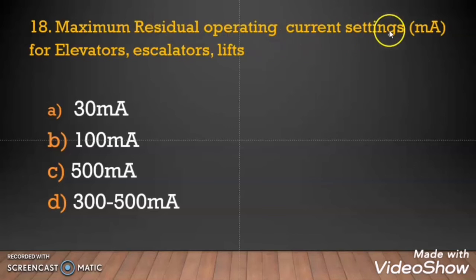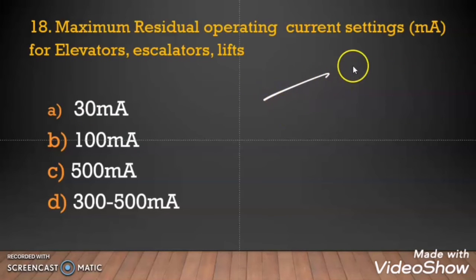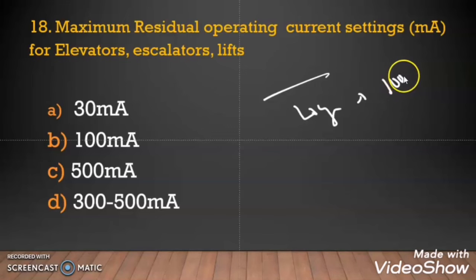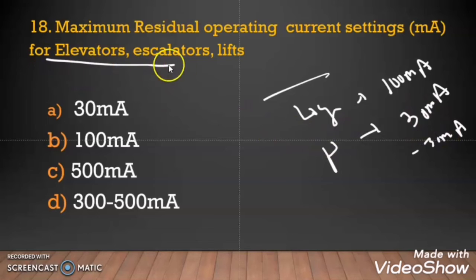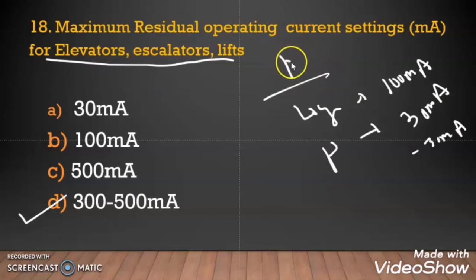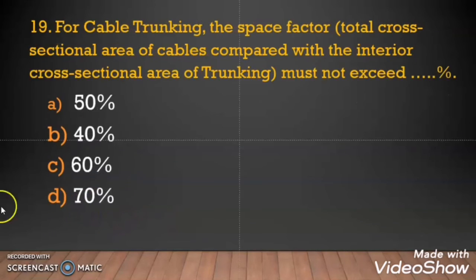Question 18: The maximum residual operating current setting for elevator, escalator, and lift. As per ADDC regulation, different loads have different residual operating current settings. For lighting, the maximum is 100 mA; for power loads like fridges, washing machines, and water heaters, the maximum is 30 mA. For elevator, escalator, and lift, the correct answer is 300 to 500 mA. You need an RCCB with a sensitivity rating of 300 to 500 mA for these loads.